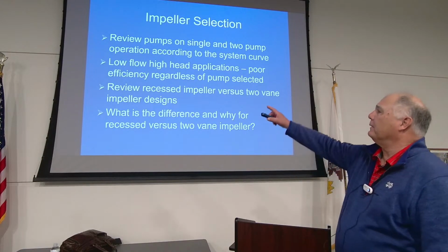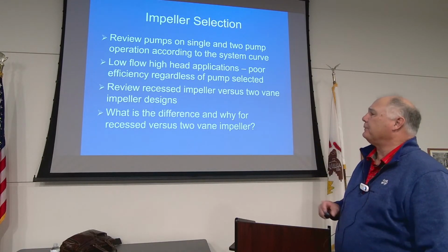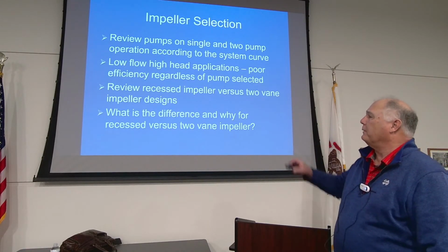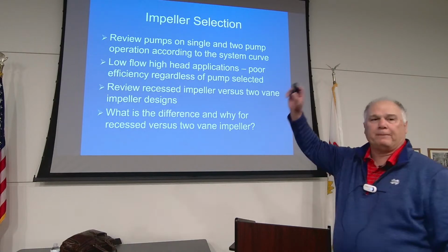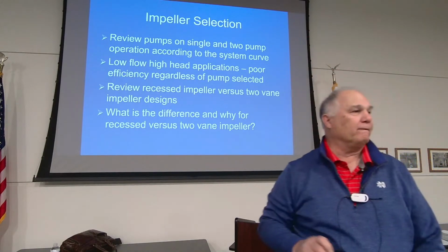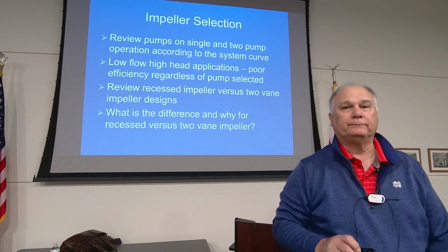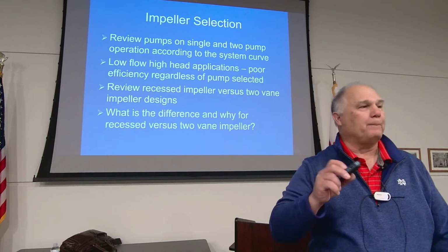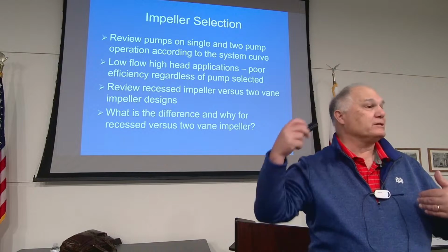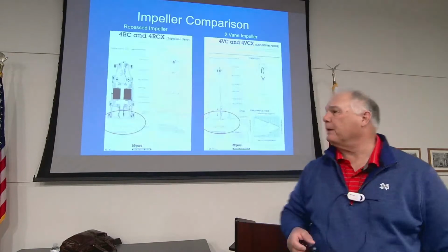So we've got to worry about low flow, high head applications for cavitation. We've got to understand what we're doing. How many people have heard of a recessed impeller? A vortex or recessed impeller? For small pump stations, I believe this makes sense, but we're going to talk about the different impeller options.